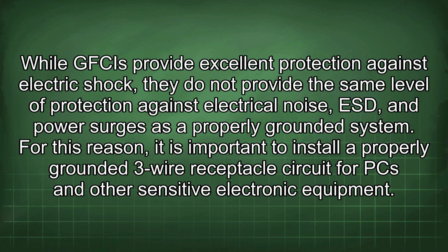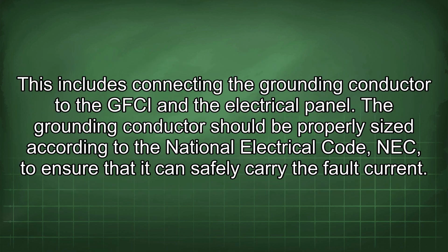While GFCIs provide excellent protection against electric shock, they do not provide the same level of protection against electrical noise and power surges as a properly grounded system. For this reason, it is important to install a properly grounded 3-wire receptacle circuit for PC and other sensitive electronic equipment. This includes connecting the grounding conductor to the GFCI and the electrical panel.